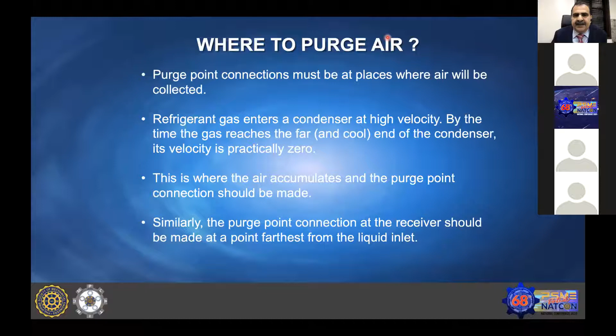But at the end of the condenser, the ammonia gas velocity becomes almost zero. It gets converted to the liquid, and air remains the same. So if you take a purge point at the outlet of the condenser, the possibility of getting air is more. Same thing happens at the receiver, where air is at the furthest point from the liquid entry point to the receiver.